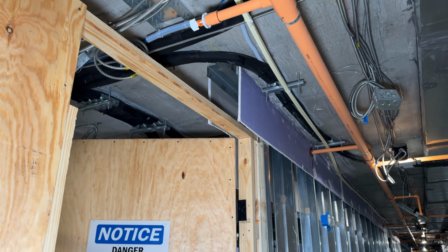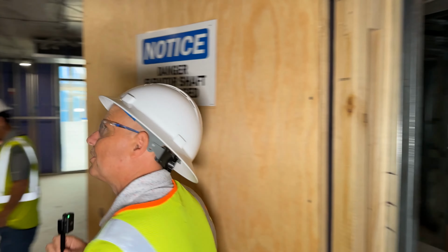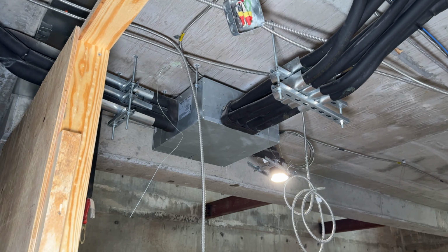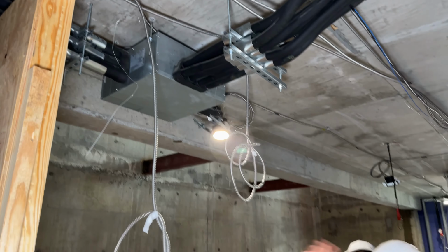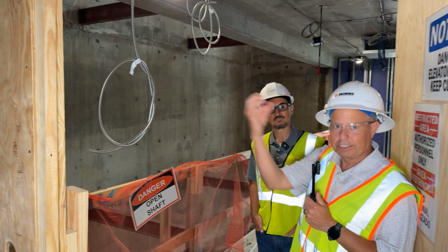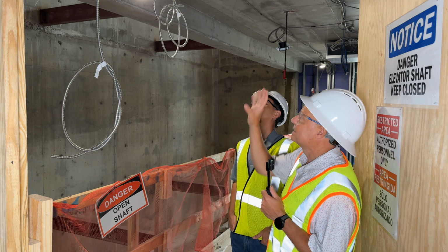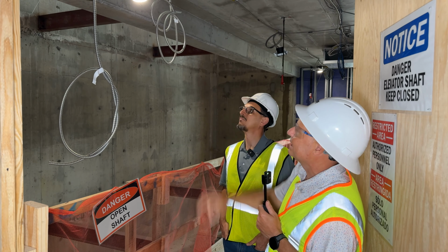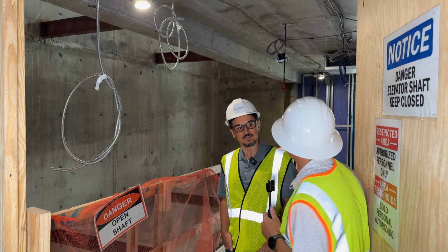And I think Anderson's probably one of the largest VRF installers in the DC market. Right. So their staff has learned all these little secrets of how to make these things successful and how they work, as well as what makes it economical. So you'll see some designs where they'll actually put an HR box in every single apartment, but that adds a lot more brazing, a lot more piping, more branches. So we like the 4-port because it's small and compact. You get multiple units, and it seems to be one of the more cost-effective ways to do at least a multifamily type of application. Yeah, agreed.